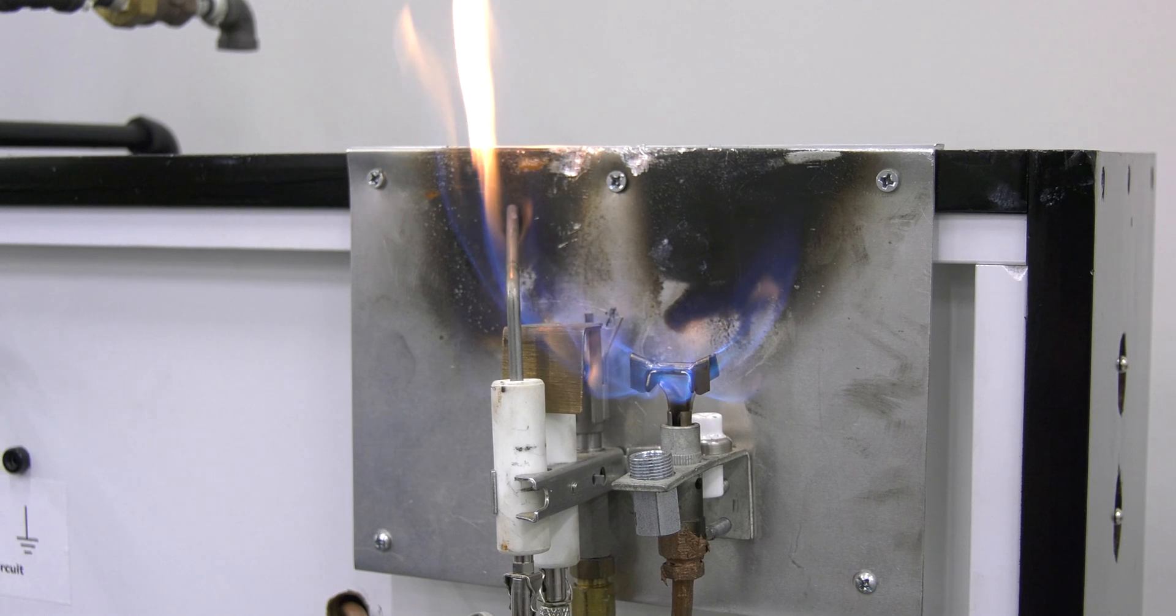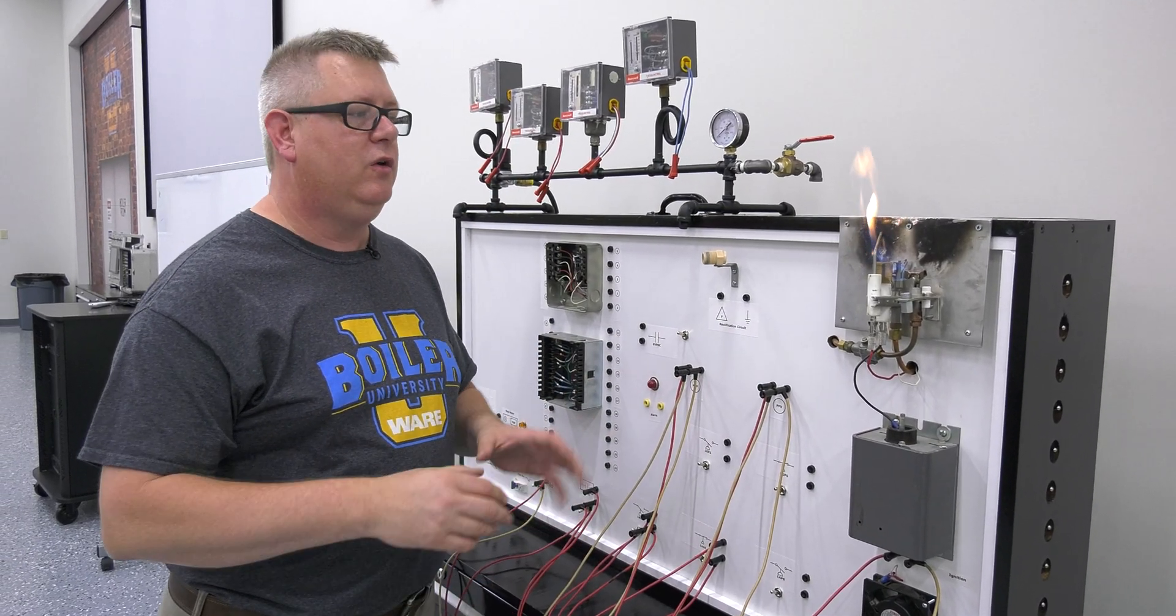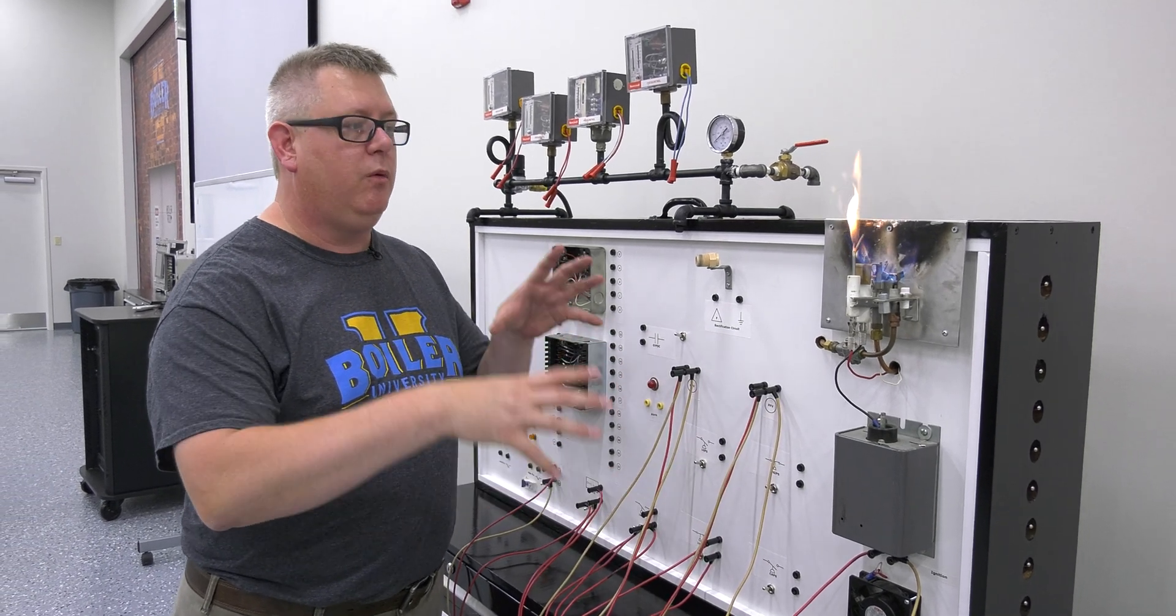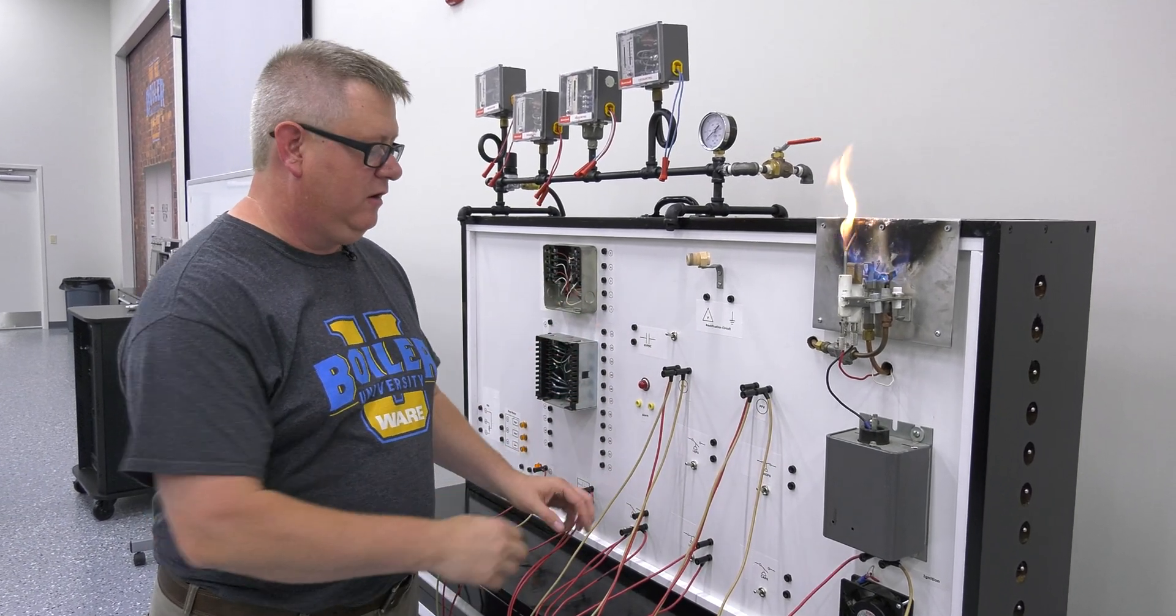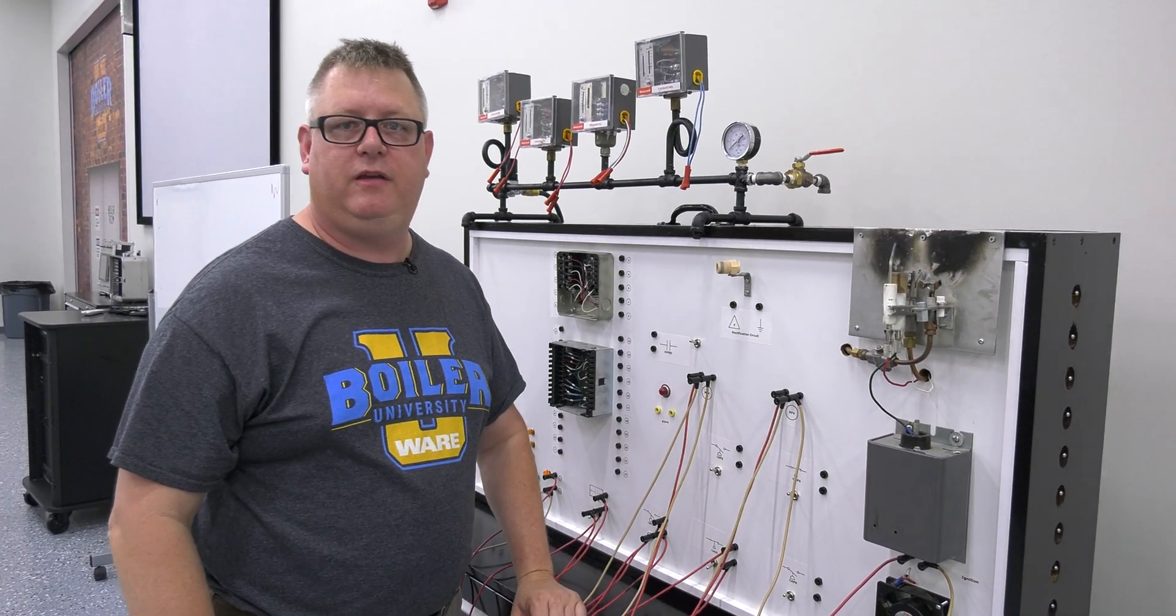This is frequently used on a very small burner. Over a certain size, we'll never use an intermittent pilot. But when our call for heat ends, both the main and pilot fuel valves will be de-energized.